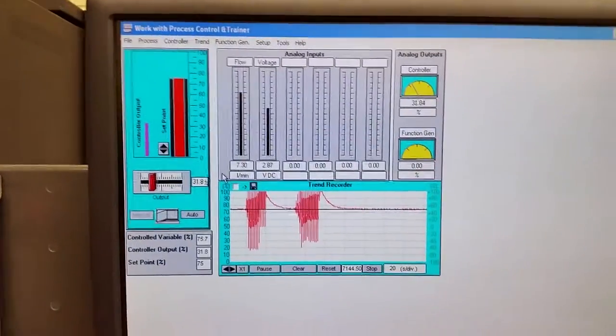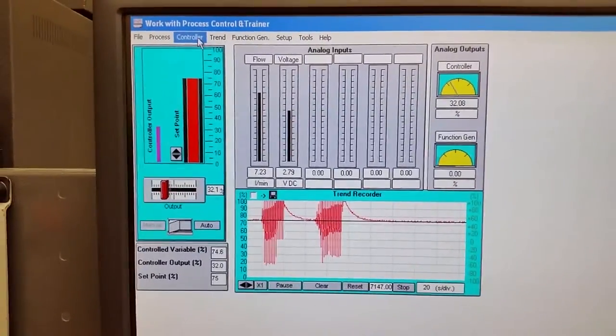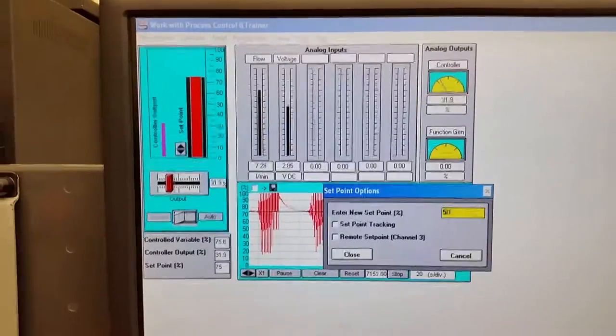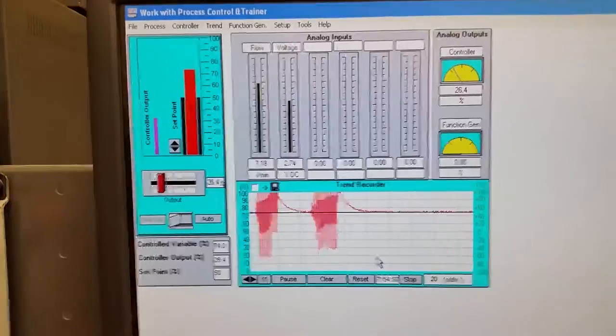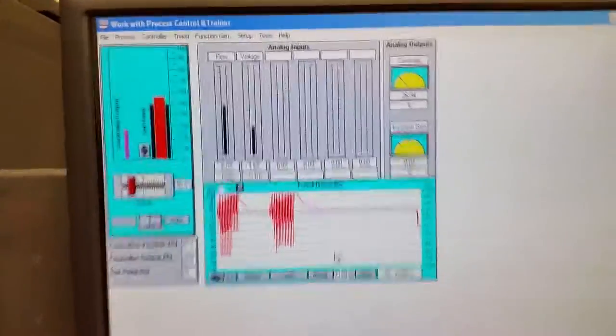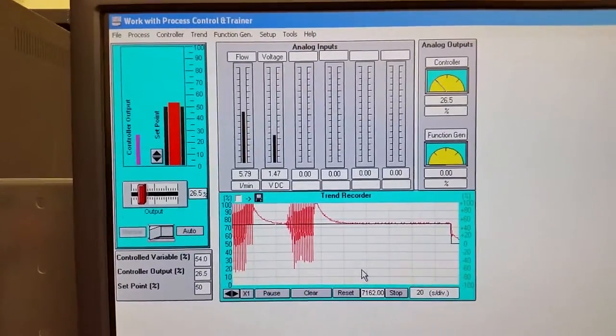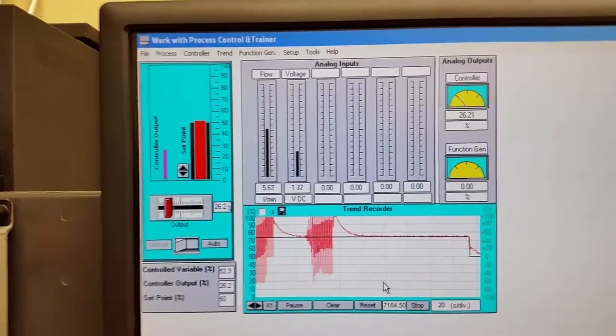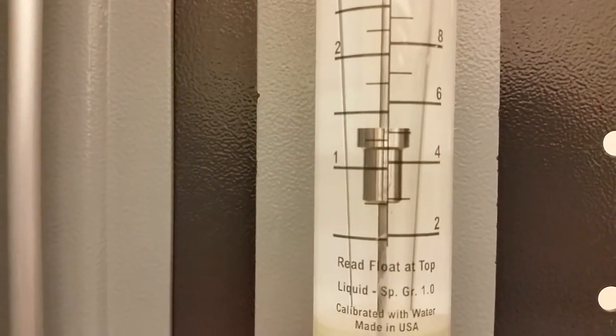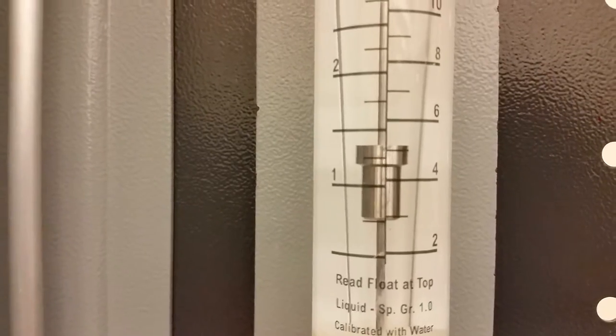We put in proportional and integral control, left out the derivative, and we're getting nice tight closed loop control. Dropping the set point to 50% should bring it down to five and a half liters per minute. You can see that's really accurate — close to five and a half on the rotameter. Excellent — nice job guys.